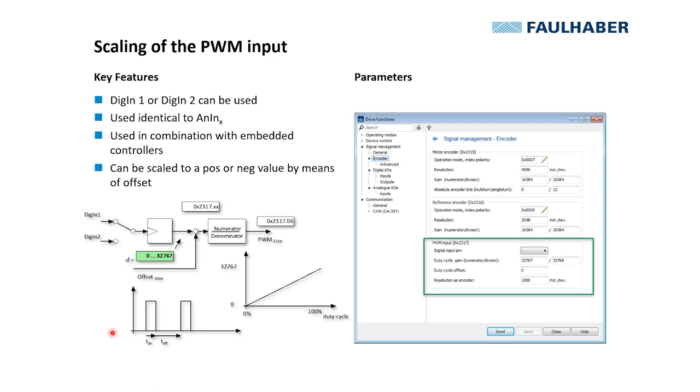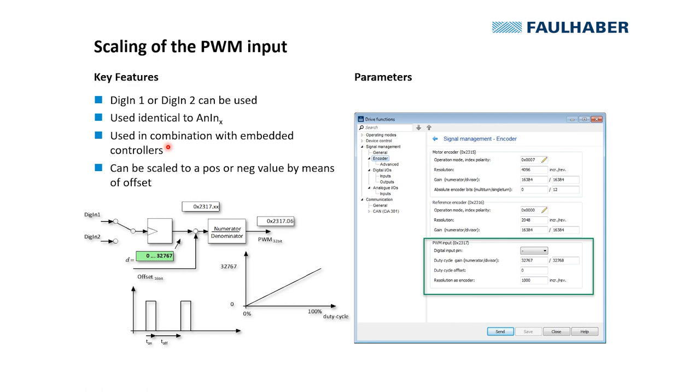So here is the summary of the scalings that we have to consider when using PWM reference signals. A single signal can either be connected to digital in 1 or digital in 2, so there's only one PWM signal that we can use. Otherwise, it can be used identical to the analog inputs, usually used in combination with embedded controllers.